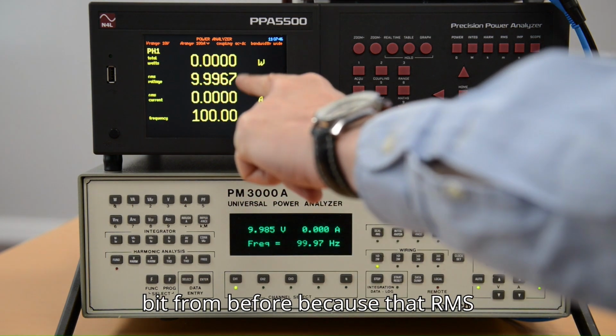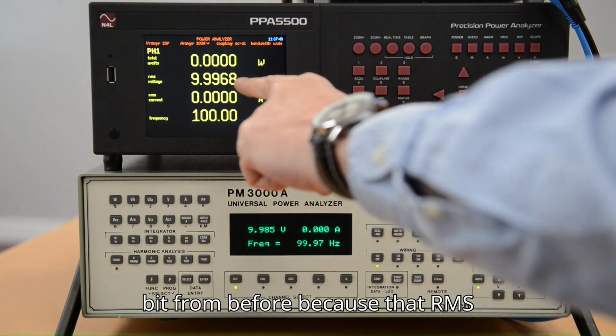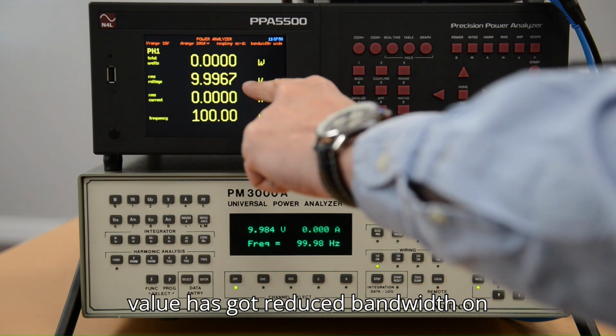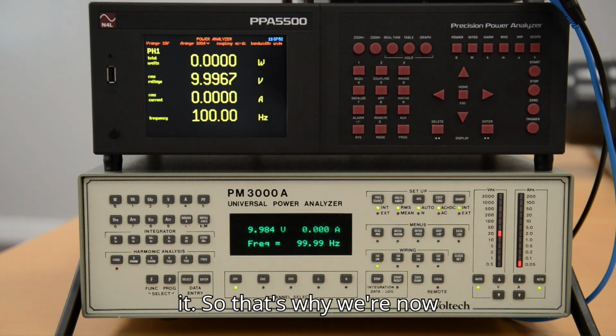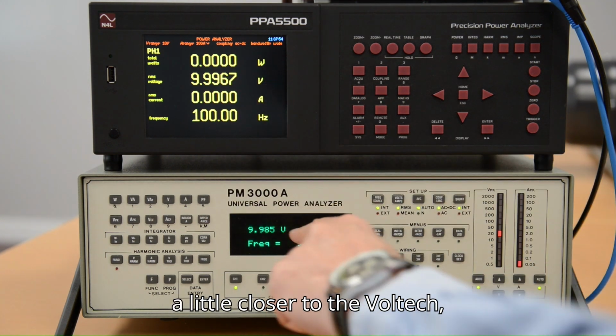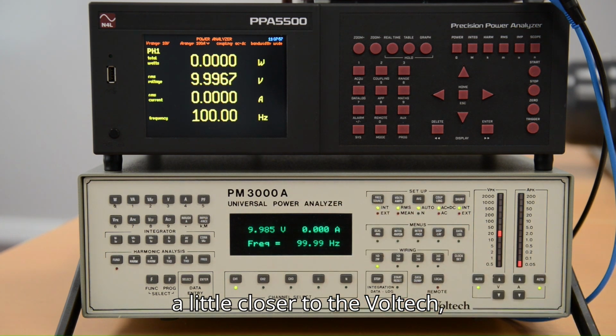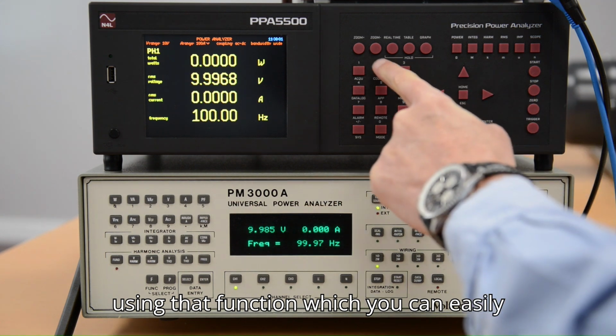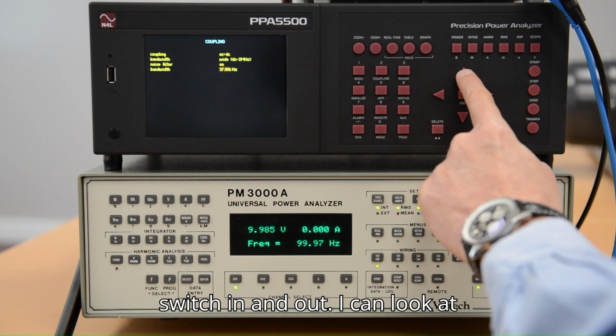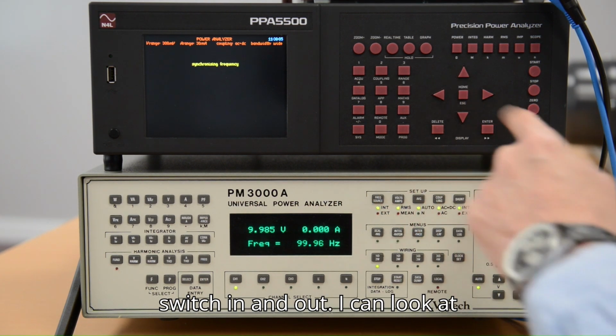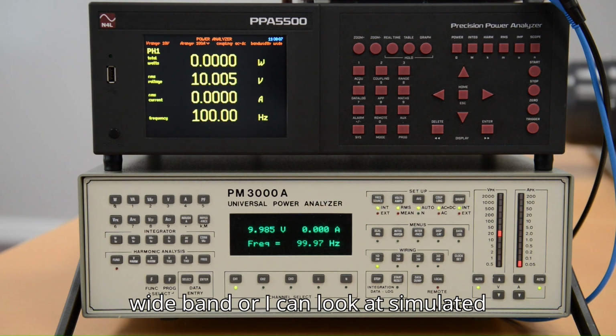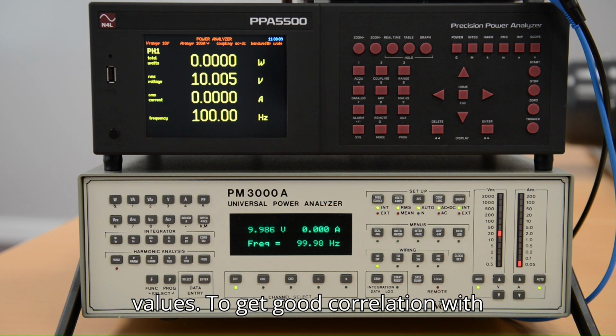This has gone down a little bit from before because that RMS value has got reduced bandwidth on it. So that's why we're now a little closer to the Voltech. But you can see that by using that function, which you can easily switch in and out, I can look at wideband or I can look at simulated values to get good correlation with other products.